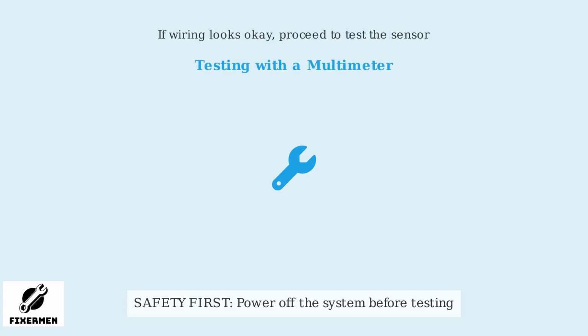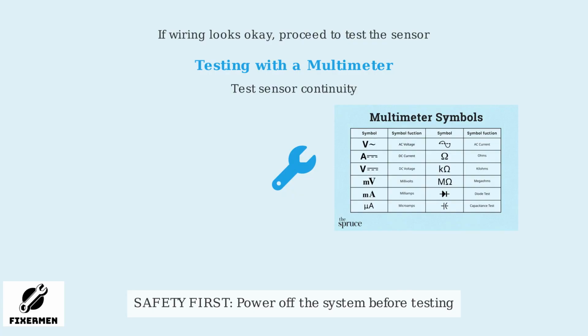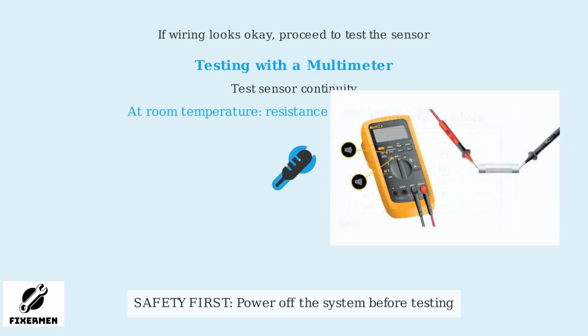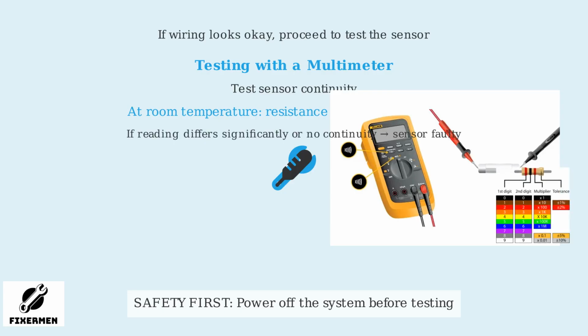If the wiring appears intact, the next step is to test the sensor using a multimeter. Ensure the HVAC system is completely powered off to avoid electrical hazards. Use the multimeter to check the sensor's continuity. Set the multimeter to ohms mode to measure resistance. At room temperature, a working sensor should show approximately 10,000 ohms of resistance, often written as 10K ohms. Connect the multimeter probes to the sensor's wires and take the reading. If the resistance is significantly different from 10K ohms, or if there's no continuity at all, the sensor is likely faulty and needs replacement.